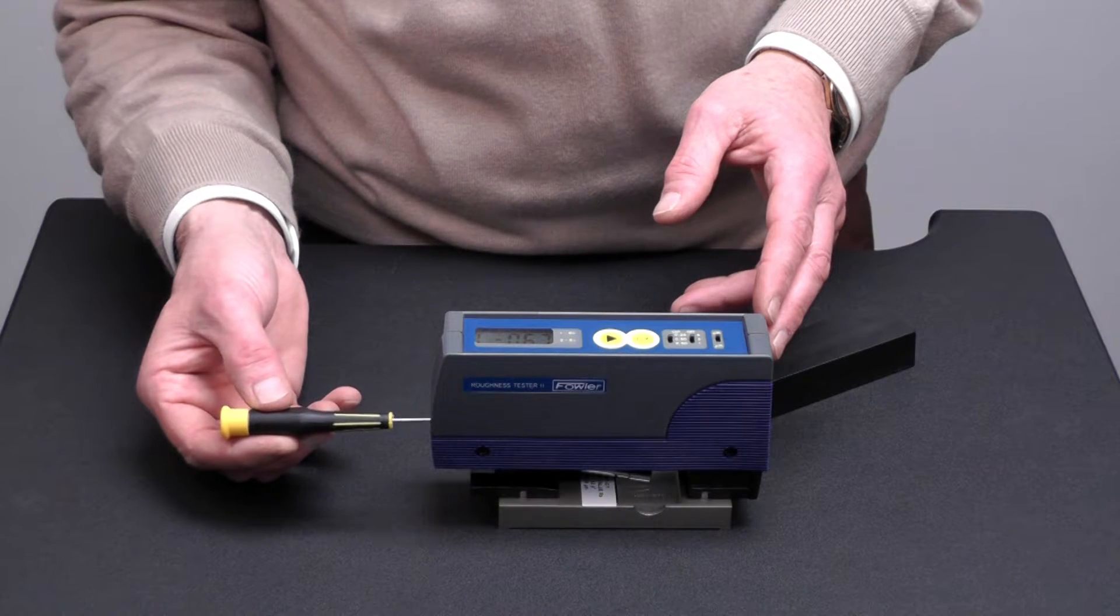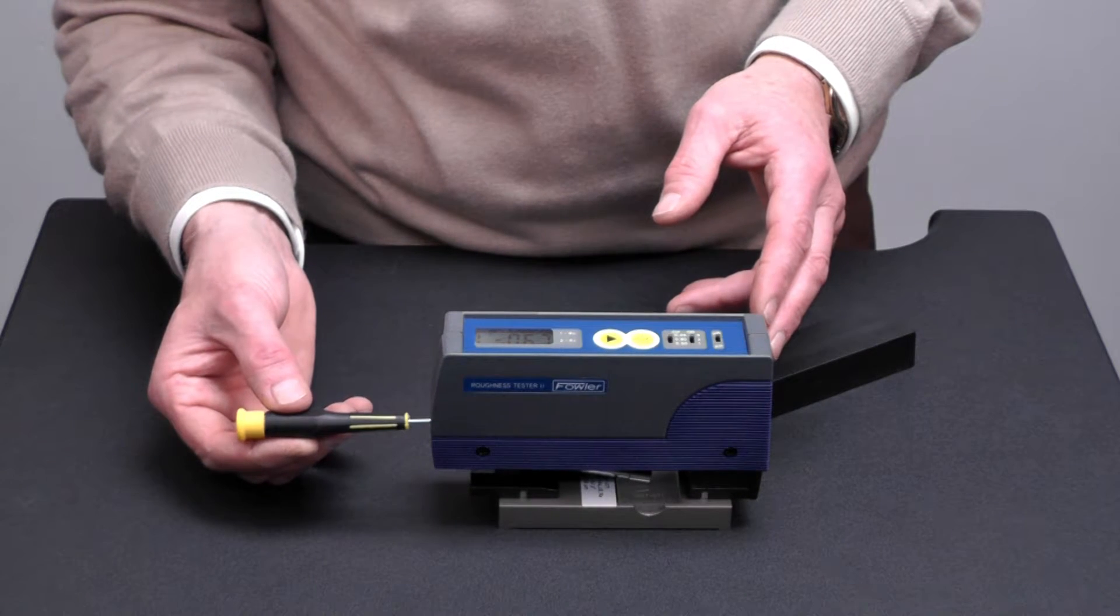If any adjustments are necessary, take the calibration screwdriver and turn the calibration potentiometer inside the unit until it reads correctly.